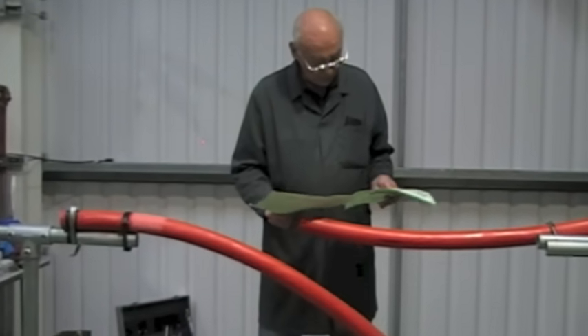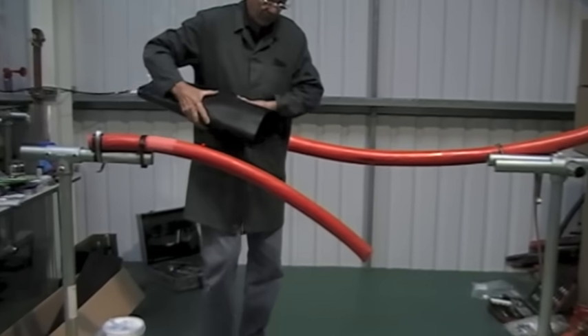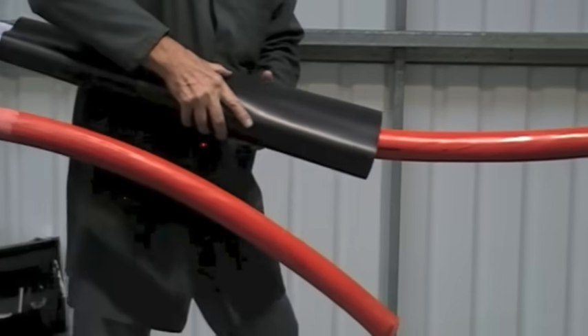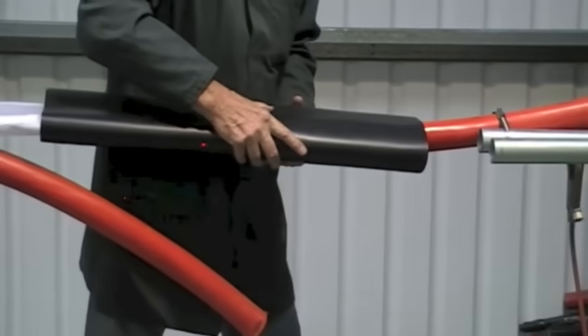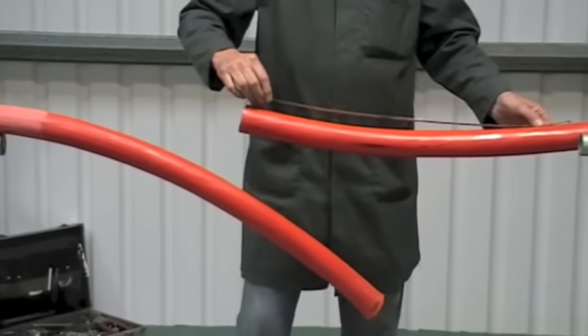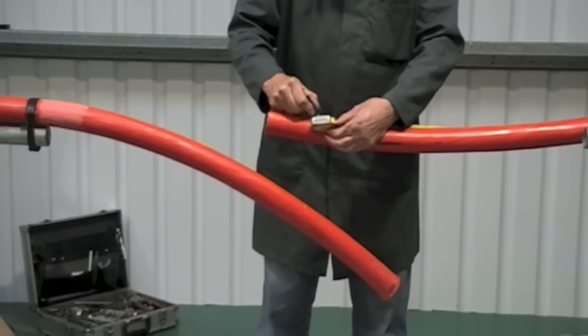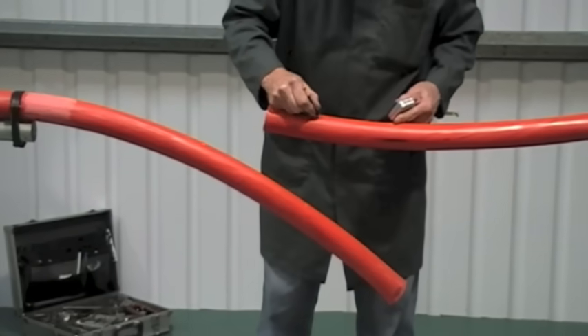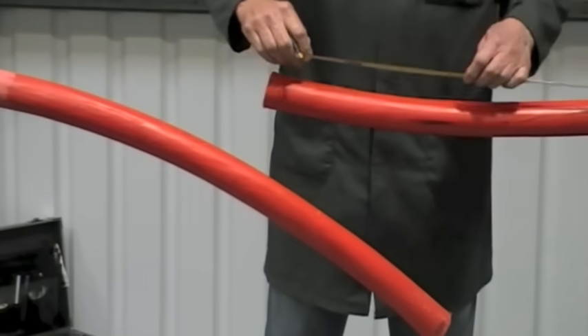We're going to show you the installation of a heat shrinkable 3 core 11kV XLPE joint. Make sure you study the installation instructions supplied in the kit and using table 1 and figure 1 mark out the outer cable jacket.